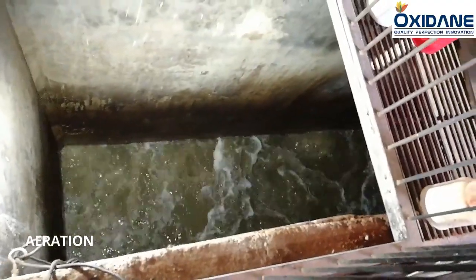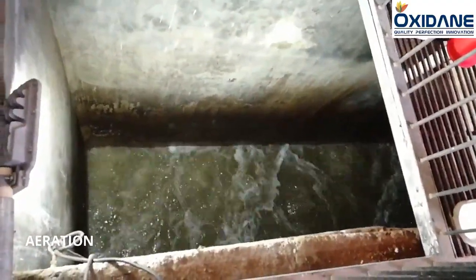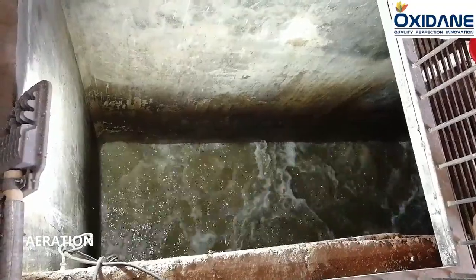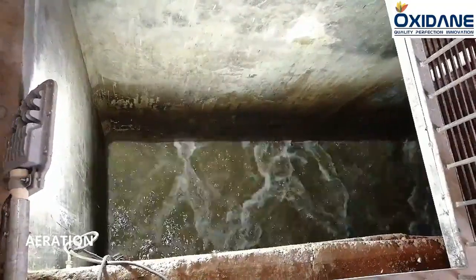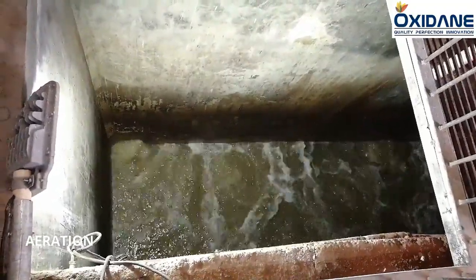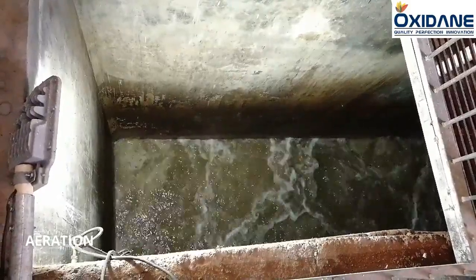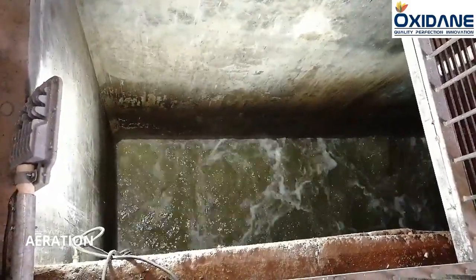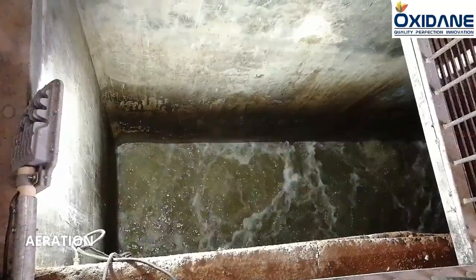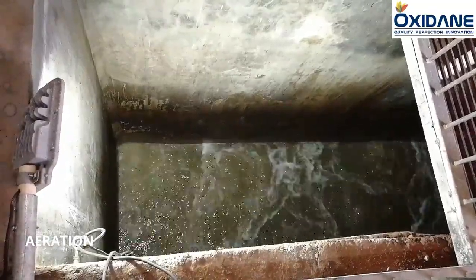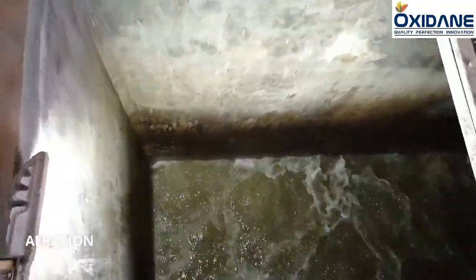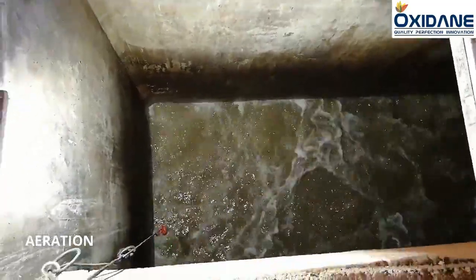Back to the equalization tank. Here continuous aeration is provided from the air blowers through diffusers, which are placed at the bottom of the tank. The equalization tank also acts as an aeration tank. Its main function is to maintain a high population level of microbes. Here coarse bubble aeration is adopted by air diffusion through perforated PVC pipes.